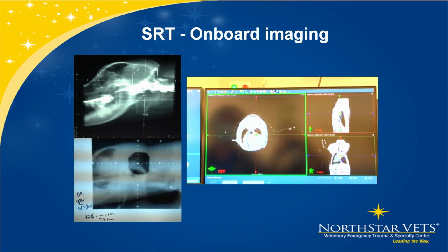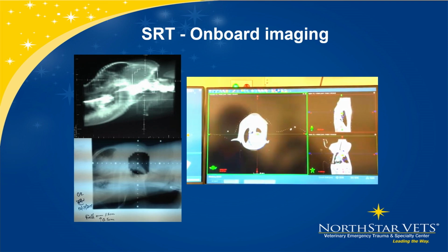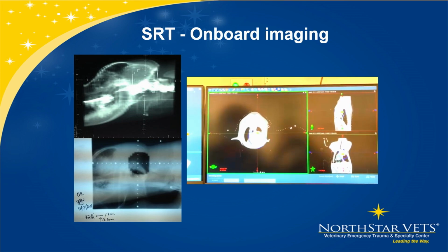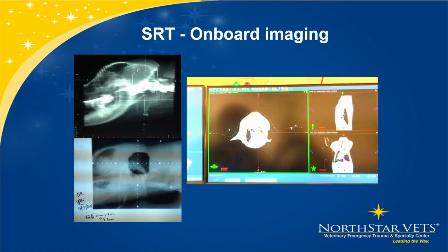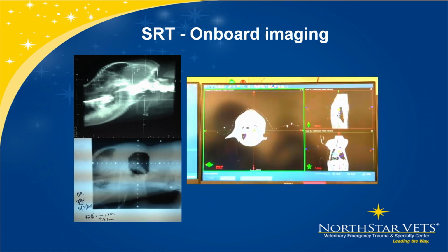But now with, hopefully this translates well on the screen, our cone beam CT, we actually have a 3D overlay, so you can see the magnification screen. The radiation therapist can take this little toggle bar right here and switch back and forth between the CT scan and the actual day of treatment. By switching in between those, they can set up the center of that beam. We're doing bone on bone, soft tissue, tumor itself, overlaying those structures. As long as that matches up exactly to the planning CT scan, we've got sub-millimeter accuracy, way higher assurance, we can now do stereotactic radiation, we can treat the patient safely.